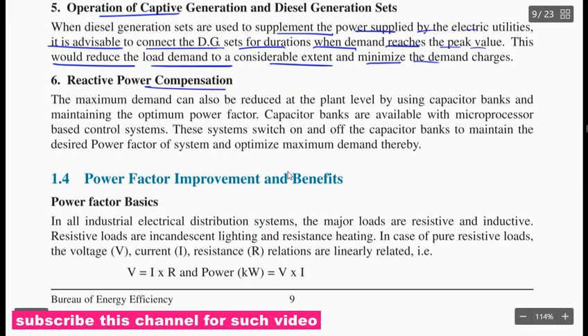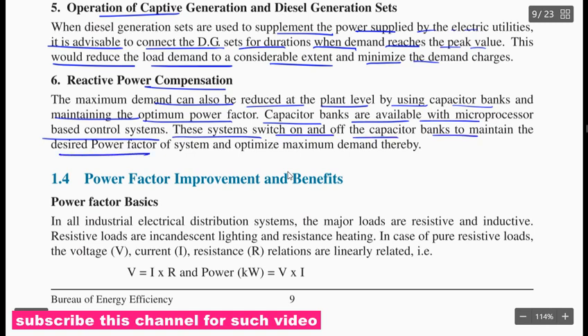Reactive power compensation. The maximum demand can also be reduced at the plant level by using a capacitor bank and maintaining the optimum power factor. Capacitor banks are available with microprocessor based control systems. These systems switch the capacitor banks on and off to maintain the desired power factor of the system and optimize maximum demand thereby.